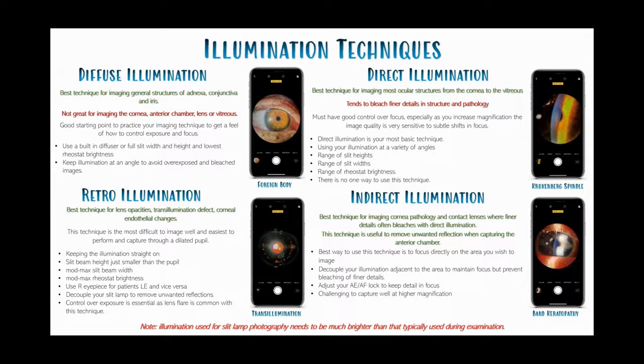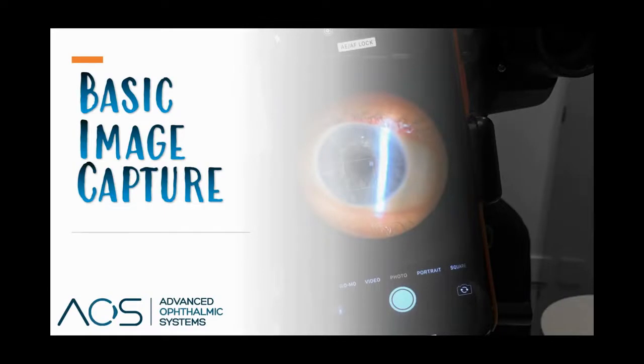Adjust your focus lock as needed on the area you're observing indirectly. At higher magnification, depth of focus becomes a challenge. Also note that illumination used for slit lamp photography needs to be much brighter than typically used during examination, so be sure to warn the patient.